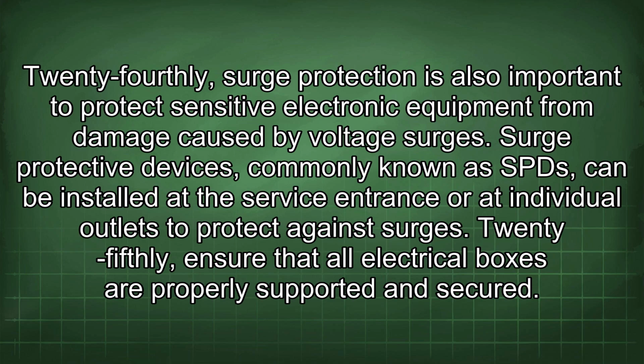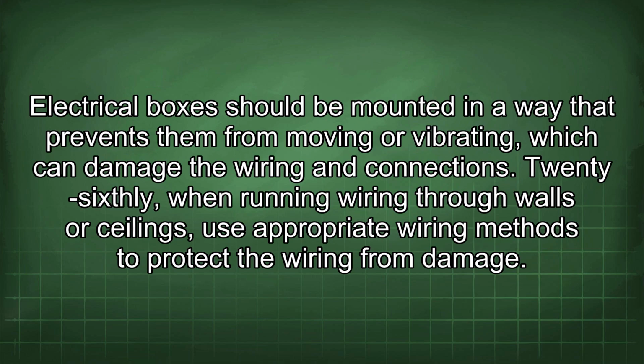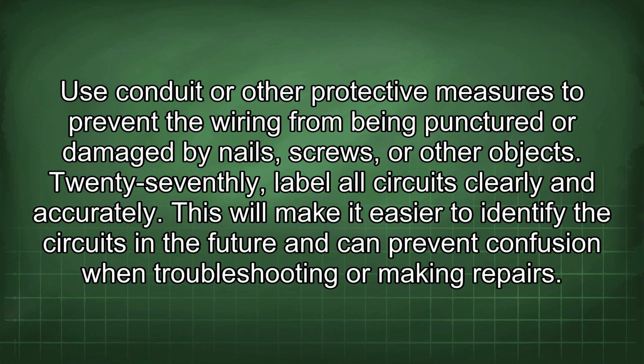Surge protective devices, commonly known as SPDs, can be installed at the service entrance or at individual outlets to protect against surges. 25th, ensure that all electrical boxes are properly supported and secured. Electrical boxes should be mounted in a way that prevents them from moving or vibrating, which can damage the wiring and connections. 26th, when running wiring through walls or ceilings, use appropriate wiring methods to protect the wiring from damage. Use conduit or other protective measures to prevent the wiring from being punctured or damaged by nails, screws, or other objects. 27th, label all circuits clearly and accurately.